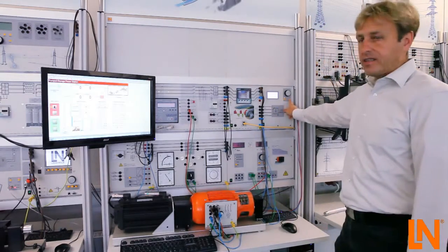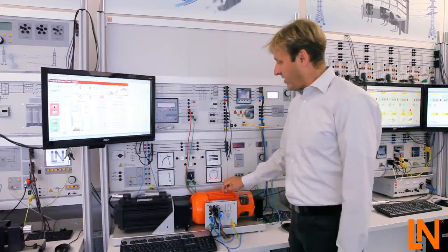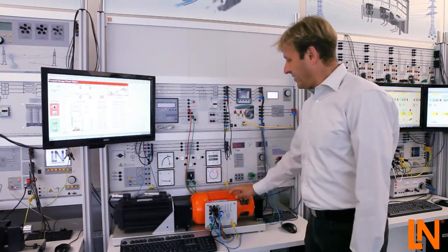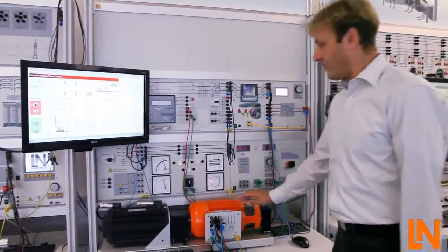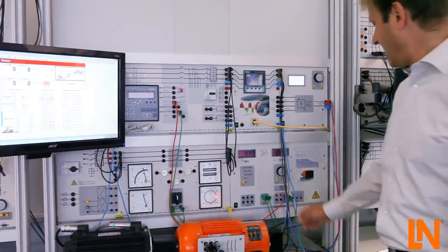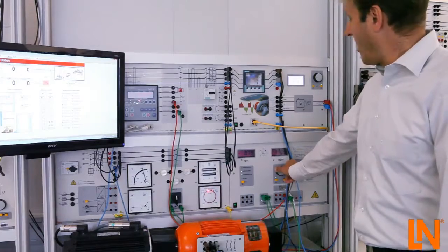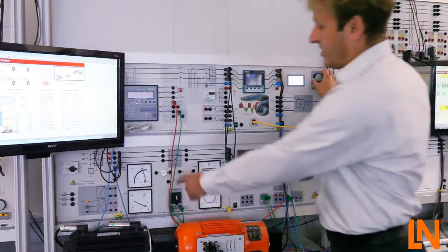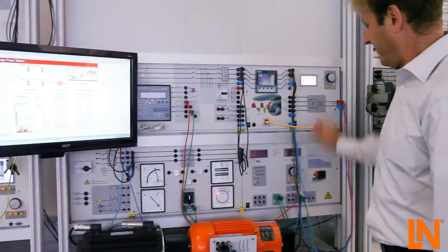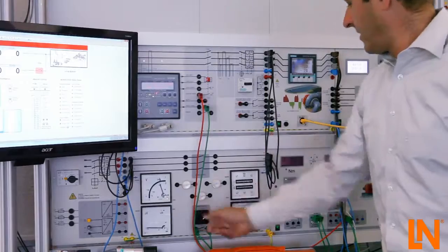Then I switch on the exciter voltage, and you see now here the synchronization unit where you can see the voltages of the generator and the mains, as well the frequency, as well the difference between the voltages of generator and mains, and the synchronous scope for better seeing how the angle is. So now I have to synchronize by changing the speed, and I have to control the voltage of the generator by changing the exciter voltage. If it's synchron, I can switch together.